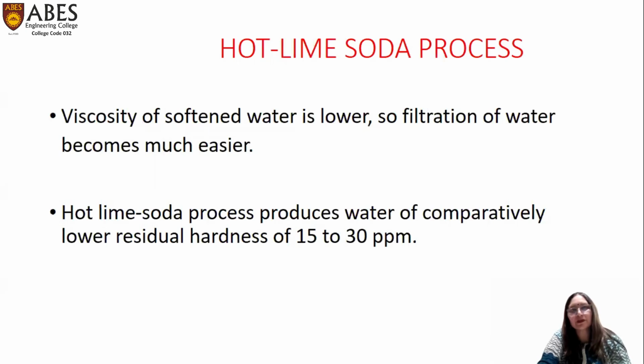Viscosity of softened water is lower. Filtration of water becomes easier. Lime soda process produces water of comparatively lower residual hardness of 15 to 30 ppm. This is the hot lime soda process.